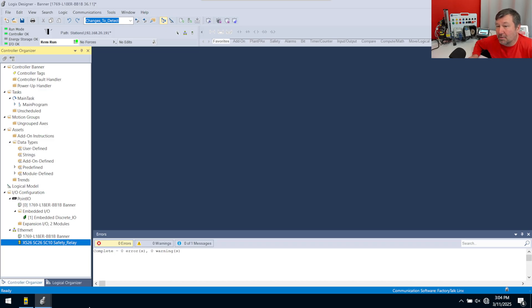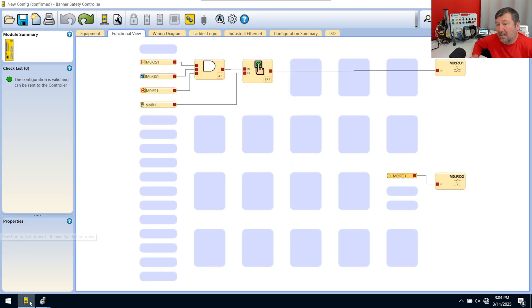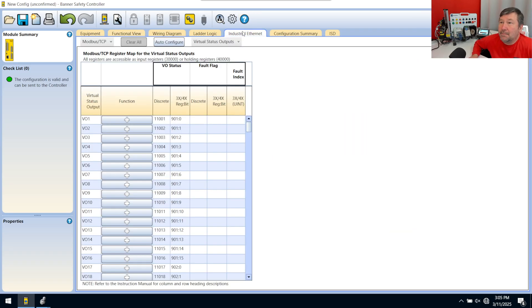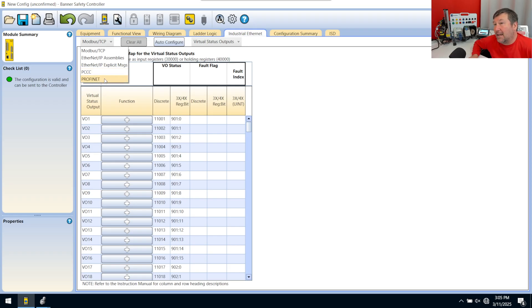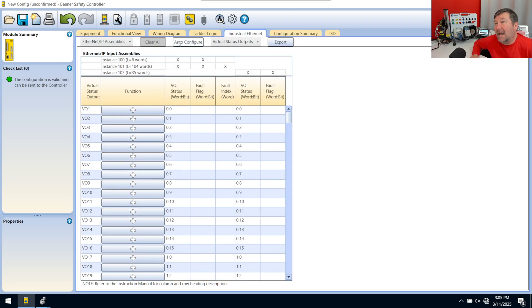We've added the module in Studio 5000 but we haven't told the Banner safety software what to do. If we go over to the Industrial Ethernet tab, it's going to default to Modbus TCP. Hit the dropdown — what's really cool is this device can do Ethernet/IP assemblies, explicit messaging, PCCC (an older protocol), and Profinet. We're going to select Ethernet/IP Assembly.